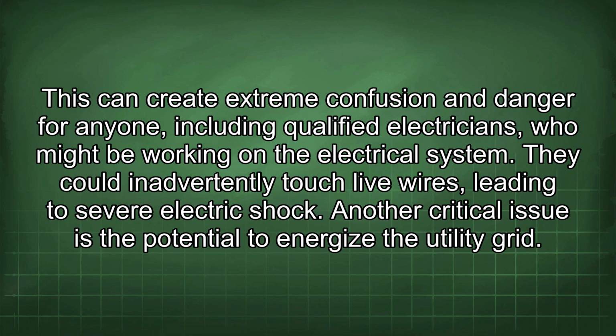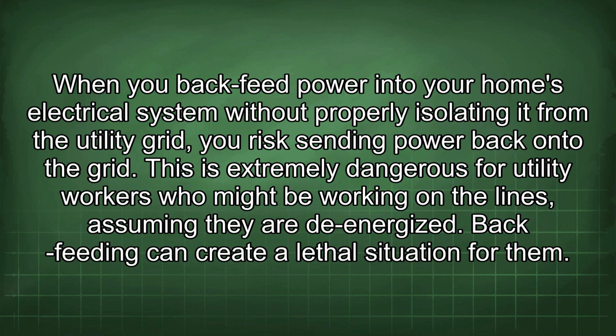Another critical issue is the potential to energize the utility grid. When you backfeed power into your home's electrical system without properly isolating it from the utility grid, you risk sending power back onto the grid. This is extremely dangerous for utility workers who might be working on the lines assuming they are de-energized. Backfeeding can create a lethal situation for them.